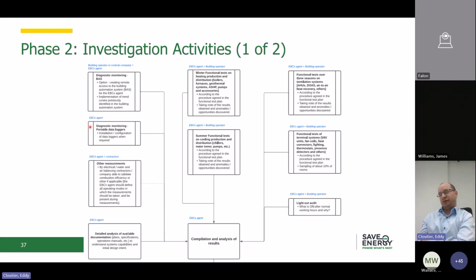We also set up diagnostic monitoring for portable data loggers, installing equipment for a specific span of time when needed, and do other measurements with a balancing contractor, electrician, and so on. The most important work of the investigation is the functional tests, usually accomplished over at least two consecutive seasons, and even better, three. This lets us see the system operate during summer, winter, and the shoulder season, since HVAC systems usually operate in different modes throughout the year.